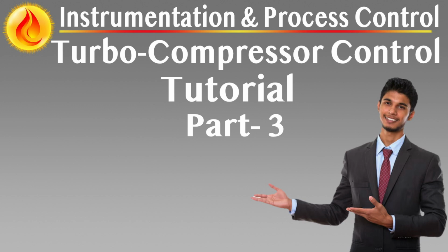Override pressure control and controller decoupling, safeguarding system integrity through hierarchical limits and independent loop architecture. Override pressure control. The Turbo Compressor Control System, TCCS, includes a configurable override pressure control function to prevent the process from exceeding defined suction or discharge pressure thresholds. This function provides an additional supervisory layer above the main performance controller, designed to activate under abnormal conditions.